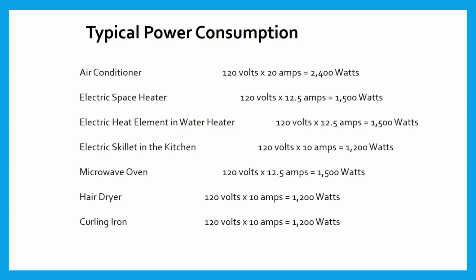But what we don't think about is, okay, we've got a receptacle maybe in the back of the RV, and maybe say on the other side of the wall or down in the kitchen somewhere or in the dining area, that wire may travel up there and feed a receptacle there. So both of those receptacles, or even more than those two, might feed off of one single circuit breaker that's only 15 amps. And so what we're trying to do is to operate a lot of these appliances off of one wire that's feeding off of one circuit breaker, that we are really taxing it and pushing it to do what it needs to do.